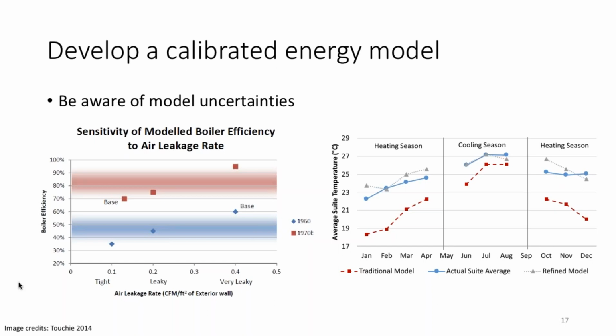The example on the right is a comparison from an energy model. The red line at the bottom shows the default temperatures, what the model would have predicted the interior temperatures to be if you left the defaults as is. But I had actually gone and monitored this building over a year and found the interior temperatures were quite different, about 4 degrees difference during the winter months. So gathering that additional field data is really important to calibrating models.